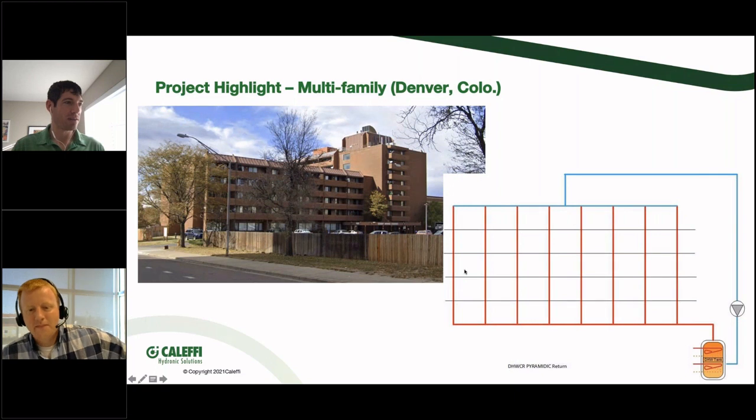So, you had mentioned a couple things. I'll go back to this picture. The pinholes: if you just triple the size of that pump, you're not solving any of those issues that Cody mentioned, except you're now creating these new pinholes behind sheetrock or whatever. And it's not even a specific material problem as much as it's just a plumbing pipe problem. It could be copper, it could be PEX, it could be CPVC. Just increasing the velocity through the roof doesn't solve anything, and it actually creates more problems.